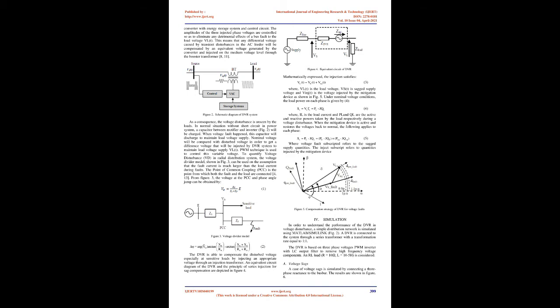The first task is to charge the energy source after a sag compensation event. The second task is to maintain the DC link voltage at its nominal voltage. Different topologies are used to charge the DC link, such as an external power supply, or by connecting the DC side of the DVR to the controlled or uncontrolled rectifier to maintain the DC voltage. The other side of the rectifier can be supplied from a main power line or from an auxiliary feeder.